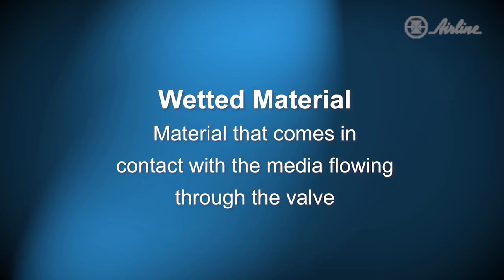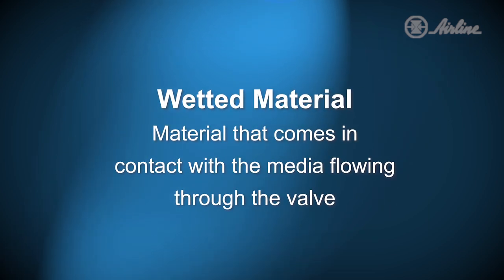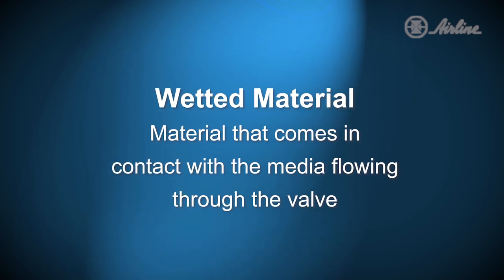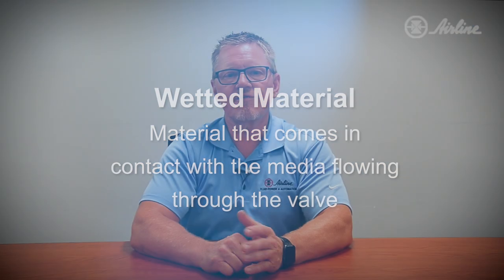The fourth term is wetted material — any material that comes in contact with the media flowing through the valve. We'll reference these terms throughout the video and discuss how they relate to the three types of isolation valves.